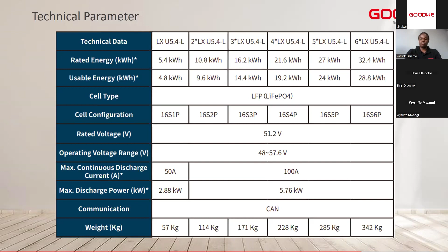Now we will dive deeper to get to know the technical parameters of the Lynx Home U battery, apart from knowing it is IP65 level. Technically, a single piece of Lynx Home U holds about 5.4 kilowatt hours of stored energy, usable 4.8. The technology used is lithium phosphate. It is low voltage, 48 to 57 volts. Charging and discharge are 50 amps, 0.5 C rated, and communication is through CAN, which is the most reliable in terms of battery communication. Compact and easier to mount, a single piece weighs 57 kg, so 2-3 people can easily lift this battery for wall mounted or ground mounted applications.